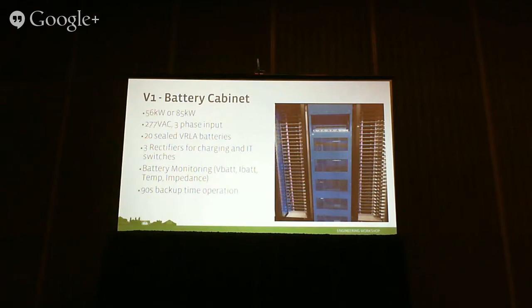That's the blue battery cabinet. Basically it's 5 shelves of lead acid batteries, 4 lead acid batteries in each shelf, so there's 20 of them there. They're all sealed, valve-regulated lead acid batteries. The cabinet itself can be 56 or 85 kilowatts, with a 277 three-phase input. It has 3 rectifiers for charging and to power some IT equipment we have, like switches that need DC voltage. We have battery monitoring, standard lead acid battery monitoring with this cabinet, measuring impedance, voltage, current, and whatnot. It's designed for a 90-second backup, and I'll talk about that in a minute.